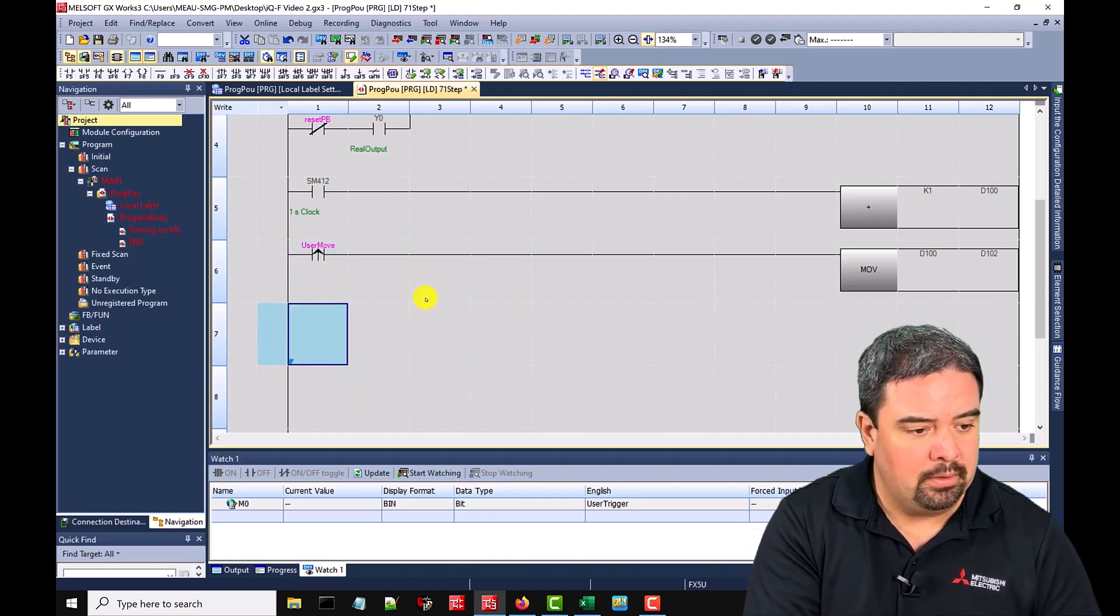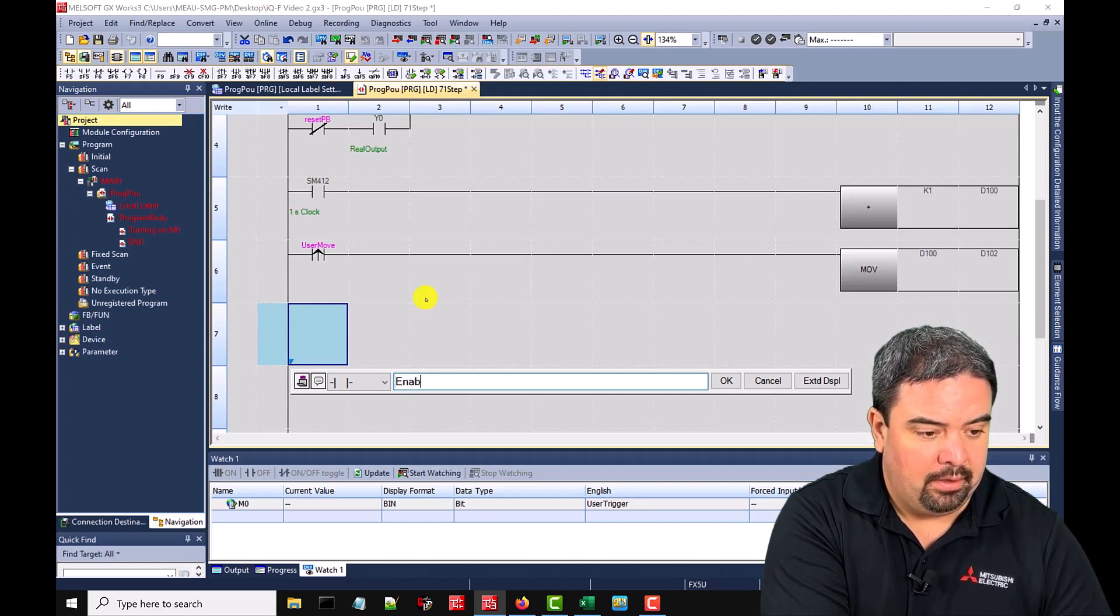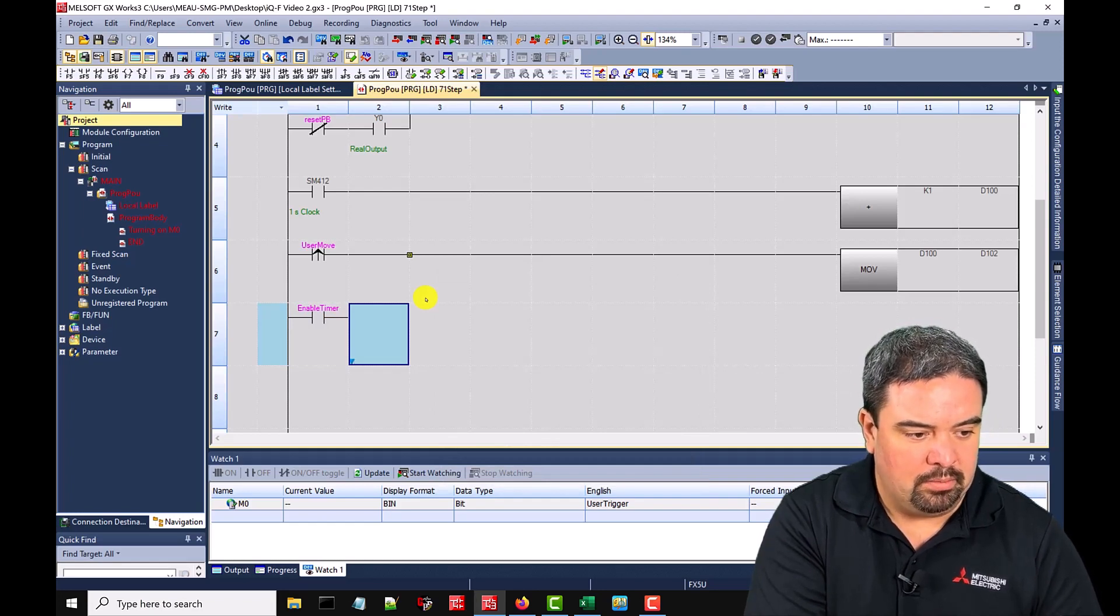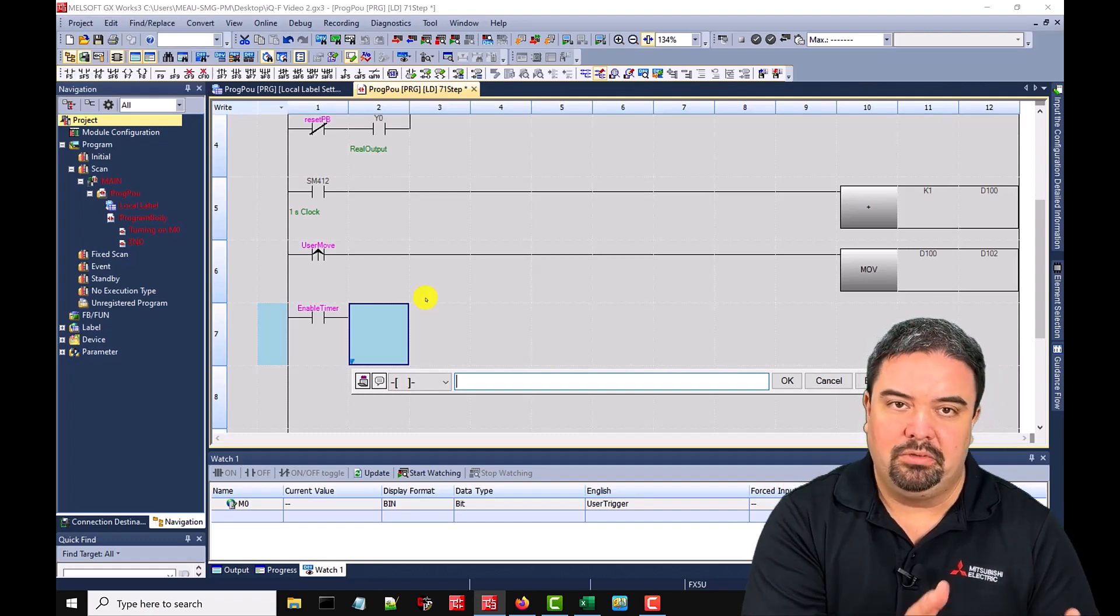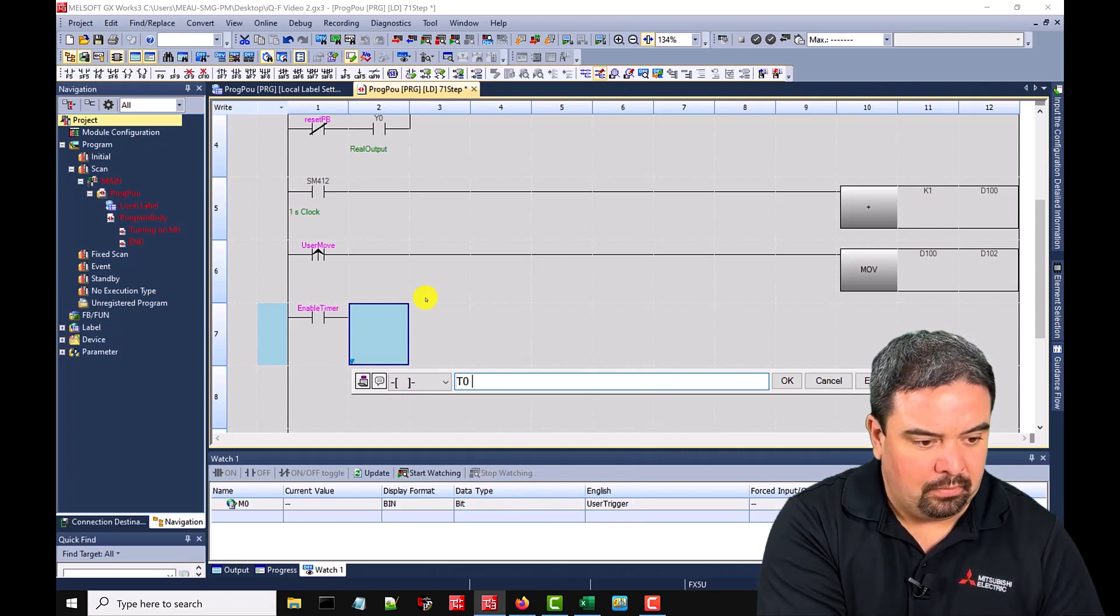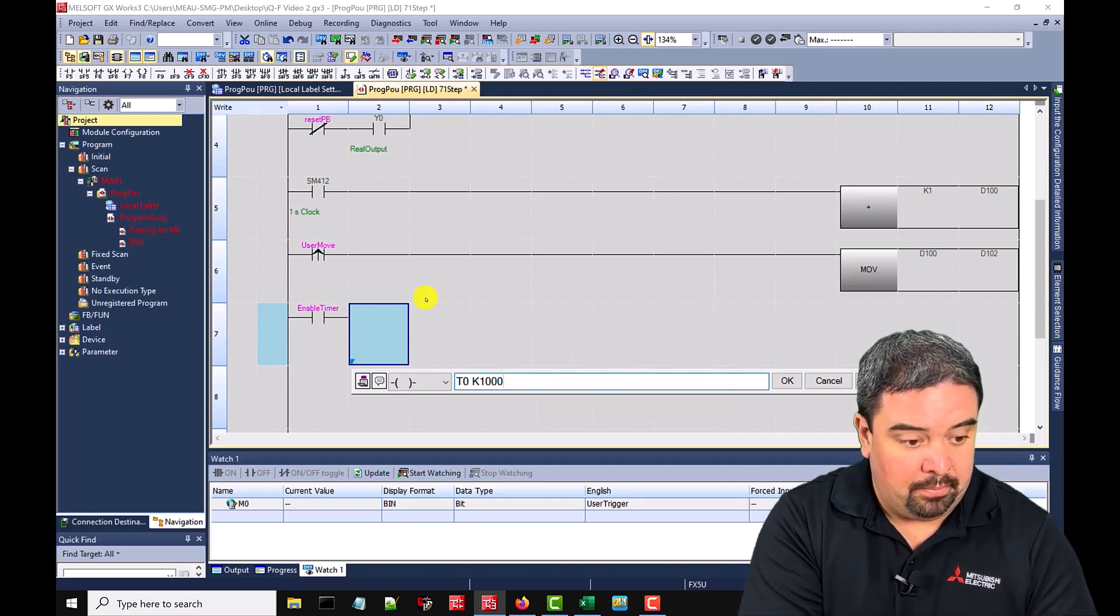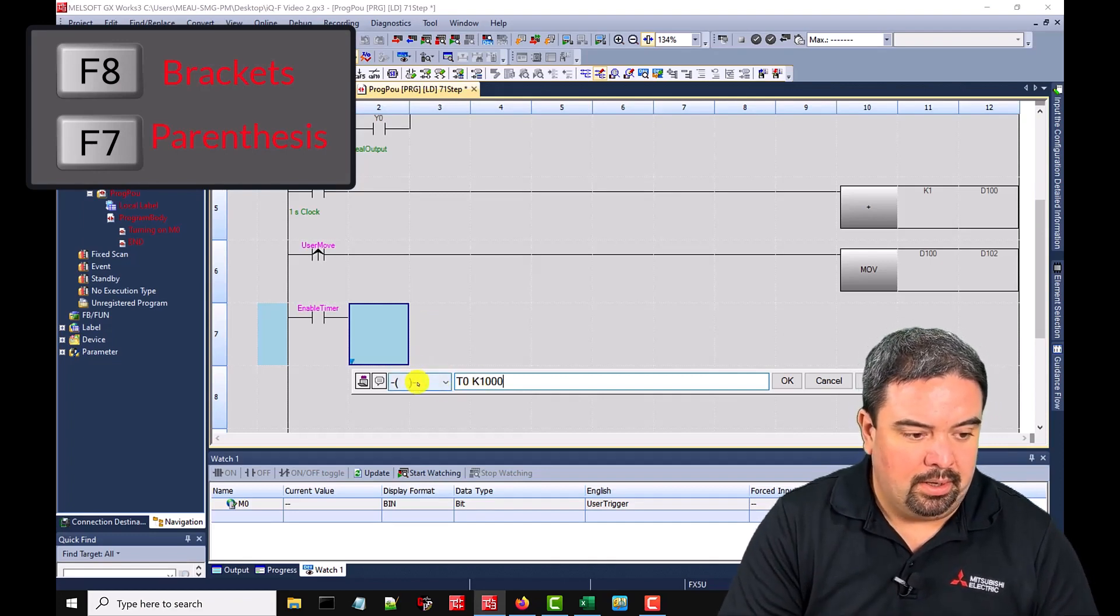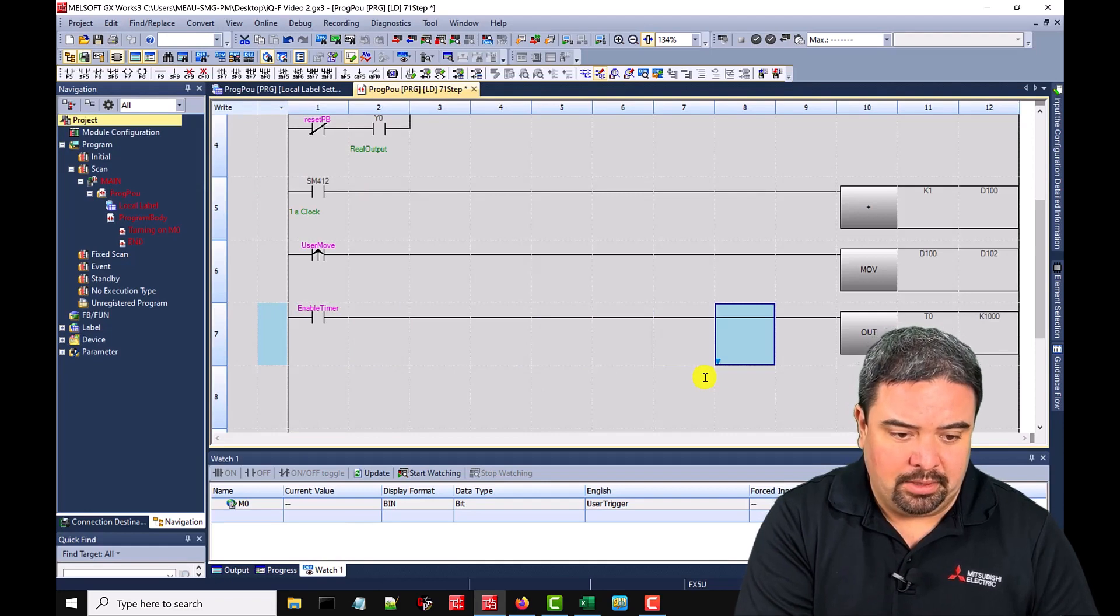Let's maybe do a timer. And I'll show you the Mitsubishi timers. So I will do normally open. That's F5, enable timer, just a local label or program scope tag, hit F8. The way that we typically would do this in Mitsubishi world is that we'll use T's. Those are timers, just like we had a D for data register or an M for a coil internal coil. So we can say T0 timer zero K 1000. So I'm going to use timer zero and count to a thousand. And actually that needs to be a coil. I had brackets, but I need a parentheses. So the parentheses create an out statement. So hit enter. And there we have our out.